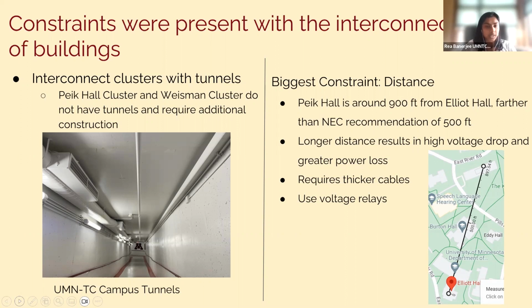So one big constraint is distance between buildings. This is a very big issue with the Peik Hall cluster. Peik Hall is around 900 feet away from the distribution array on Elliott Hall, which is longer than NEC recommendation between PV and load. The longer distance means a higher voltage drop and more power loss, so less overall output. To help with this, voltage relays can be used to keep the voltage stable at the long distance.